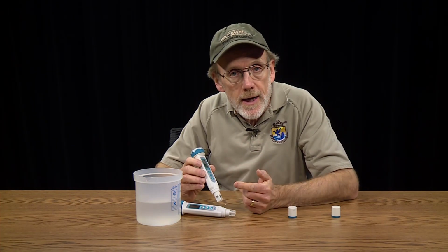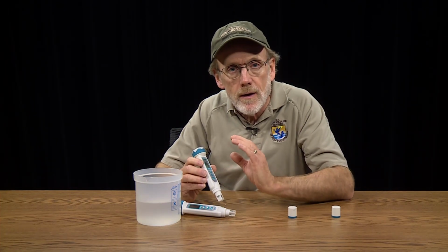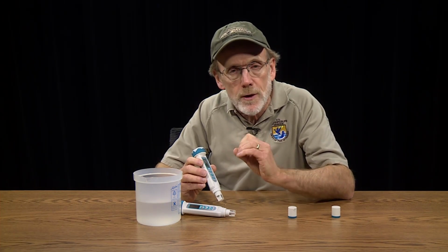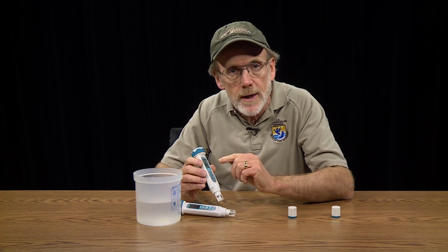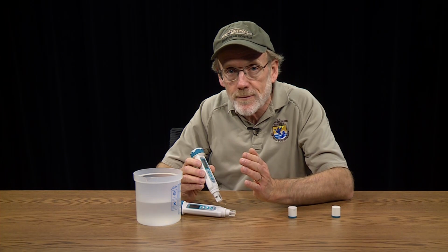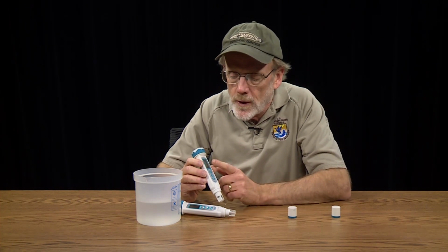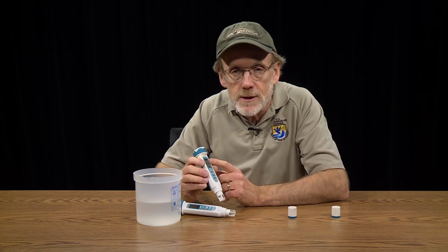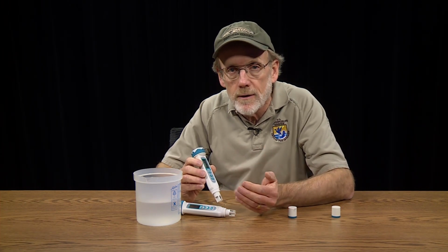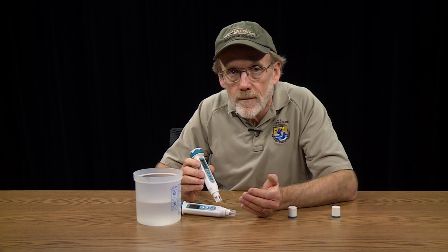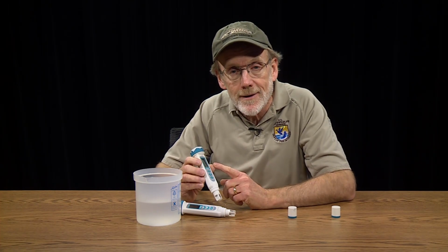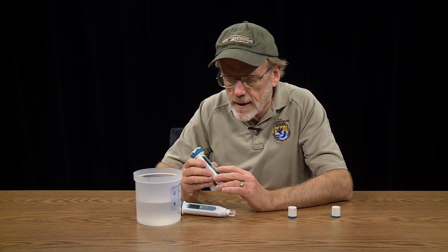So in this case, this was saying, do not adjust the temperature, make no changes to your original reading, despite the differences in water temperature and specific temperature. So what you see displayed is the actual conductivity not adjusted to some reference temperature. So that would be ambient conductivity. So let's look at the other one here.